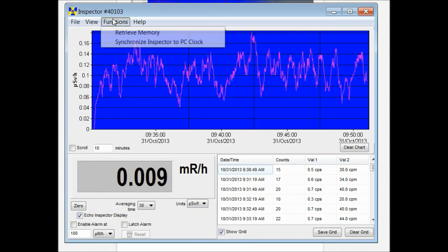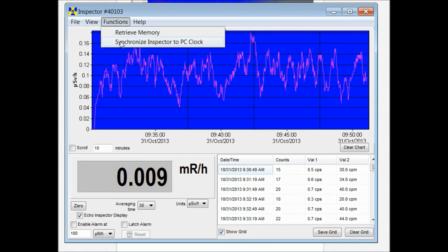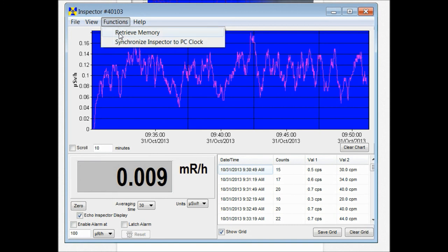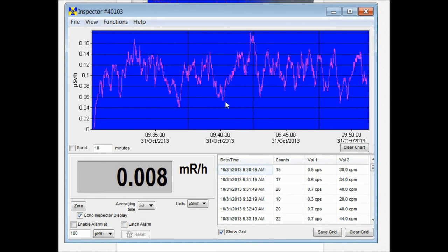Under the functions menu you can retrieve memory from the unit and you can also set the time and date on the unit. Let's just hit synchronize to my time and date on my computer. You'll hear the instrument beep twice and you know that the time and date have been updated.